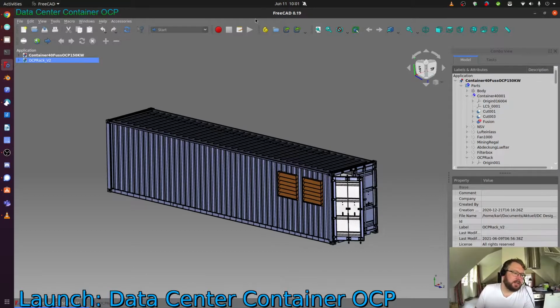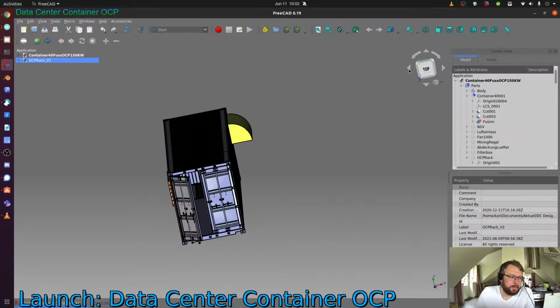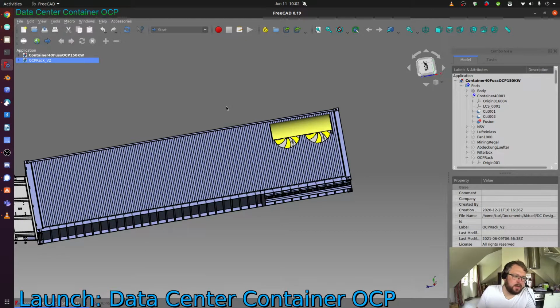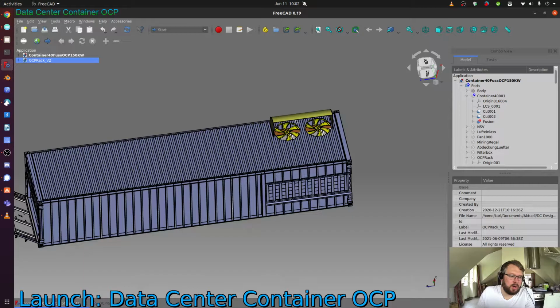As you can see, this is a direct free cooling data center, as we say in the data center business, which means you take fresh air from the outside, move it through the container and through the servers, and on the other side you get hot air out. You have two air intakes here with a filter box behind them, which we'll look at in a second, and on the back side you have a redundant fan setup that moves the hot air out of the data center. These are temperature controlled, so the higher the temperature, the higher the fan speeds, and the more air we actually move out.